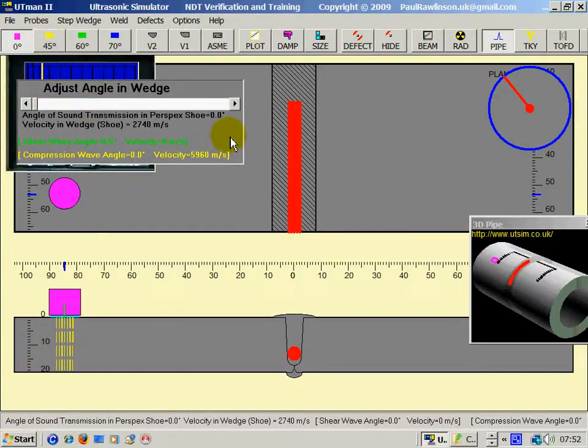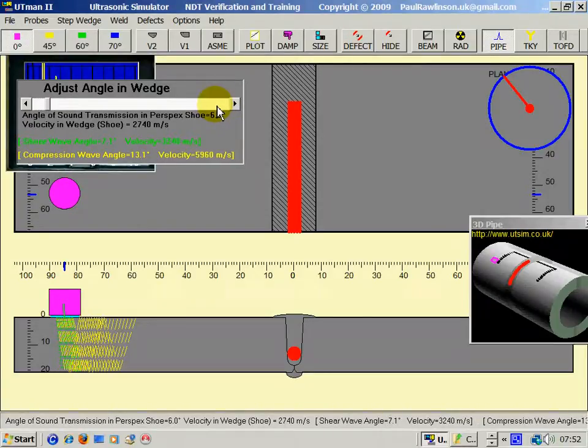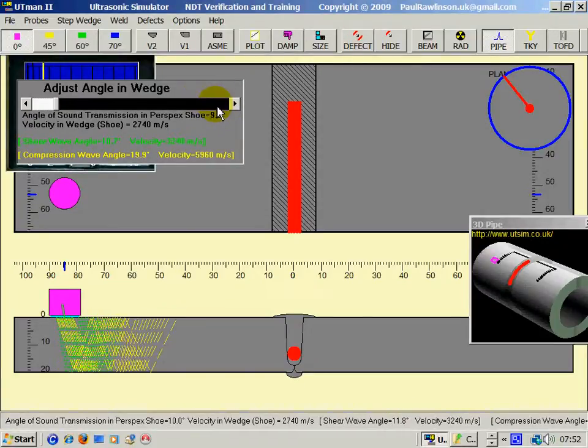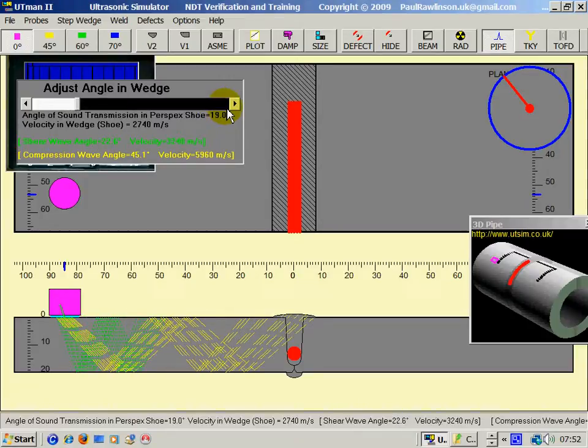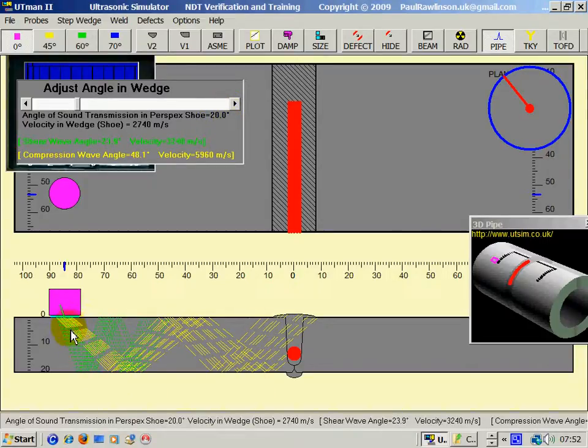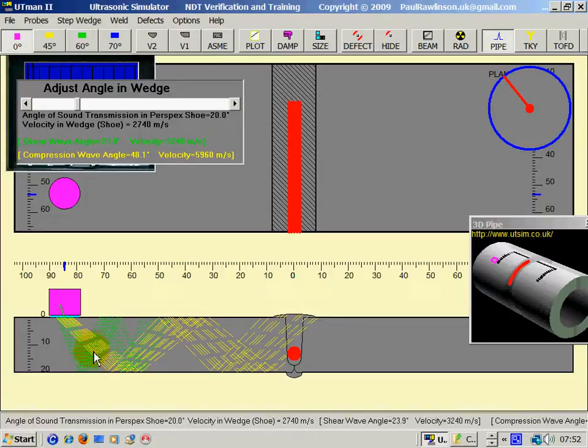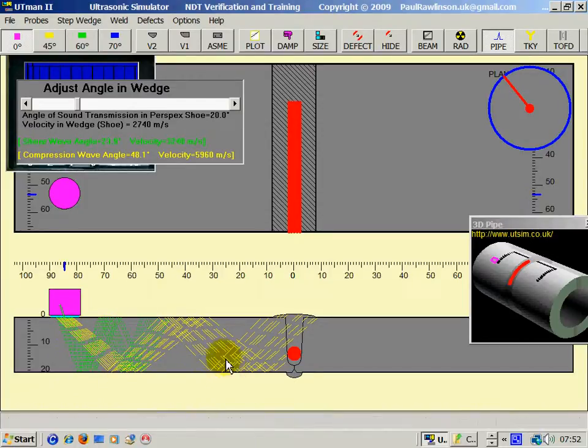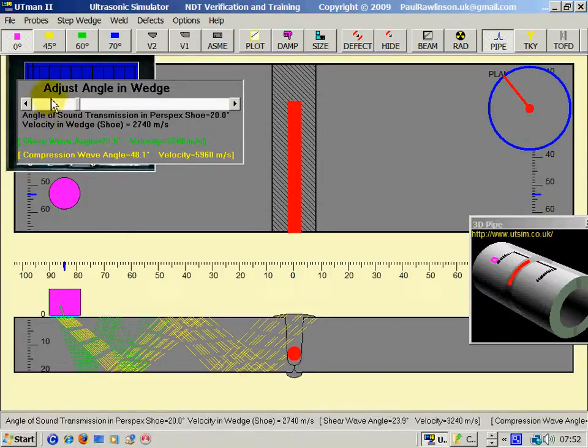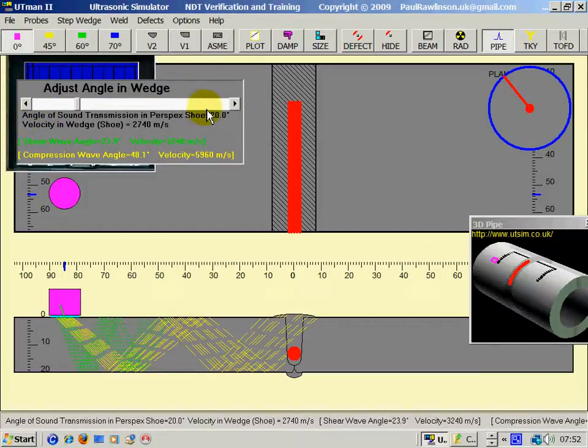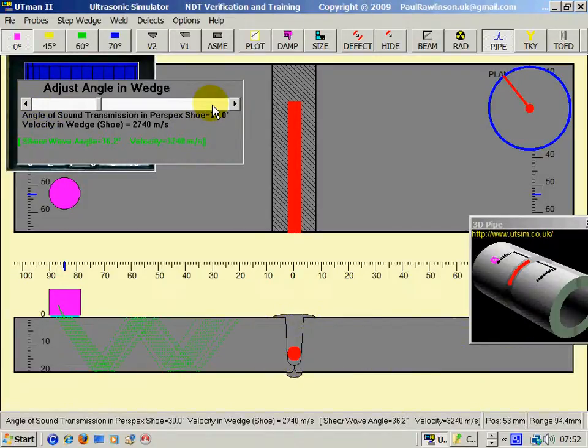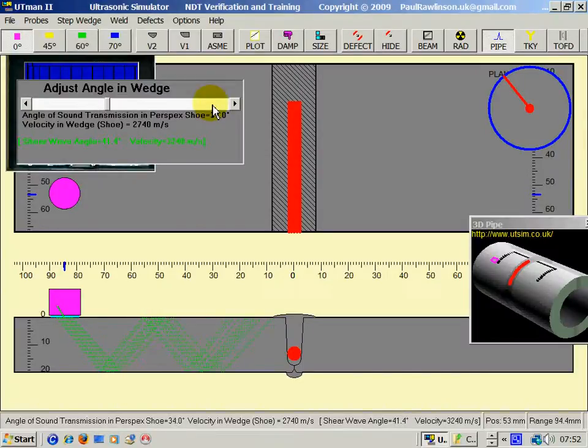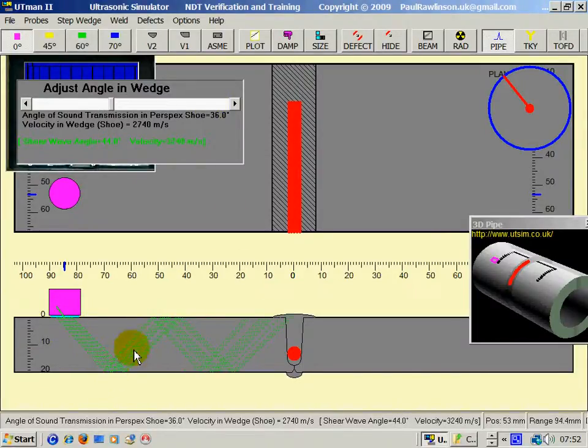Now, as I take the angle away from 90, you can see, in fact, we have two waves. We have a shear wave and we have a compression wave. For angle probes, for testing welds, we normally use the angle increased to such a level that we only have the shear wave.